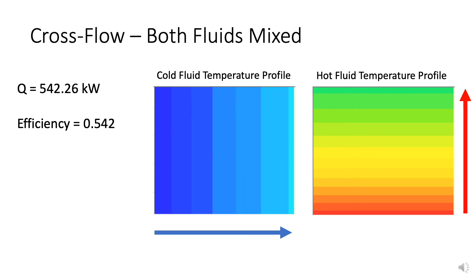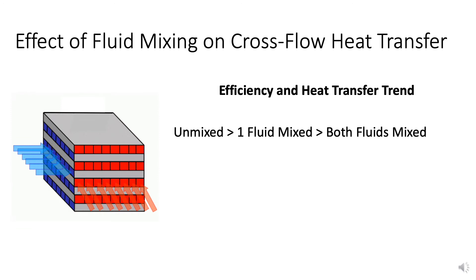Finally, there's the system where both fluids are allowed to mix. Both temperature gradients are reduced to a single dimension of travel — the cold fluid temperature profile only exists in the horizontal direction, while the hot fluid temperature profile only relies on the vertical direction. The heat transfer is reduced even further to 542.26 kilowatts, while the efficiency drops again to 0.542. Overall, the unmixed fluid cross-flow heat exchanger is the most efficient option, allowing for the greatest heat transfer. Allowing for mixing in either of the fluids decreases the heat transfer between the two fluids, as each fluid experiences greater heat transfer amongst itself in competition with the hot-cold heat transfer. In the unmixed system, more of the heat from the hot fluid is being transferred to the cold fluid, instead of being used to reheat hot fluid that has already been cooled.